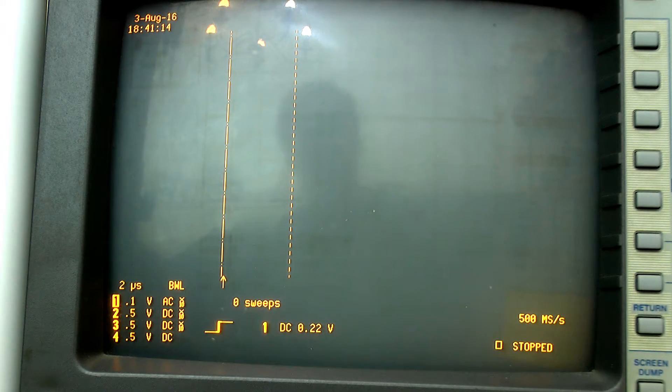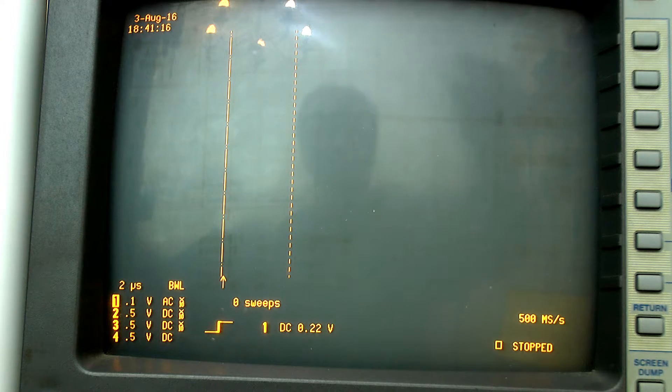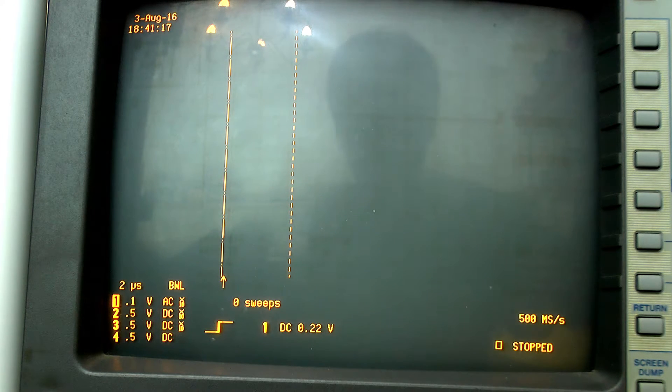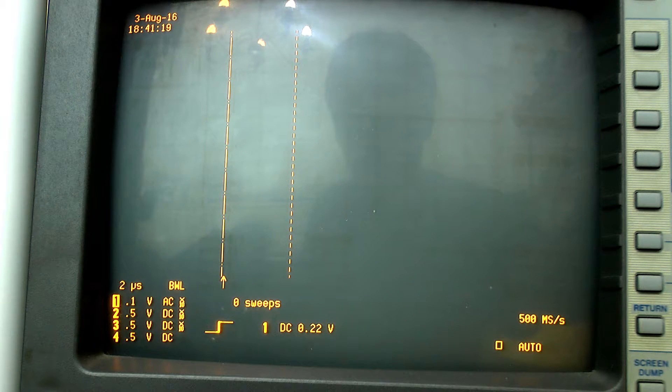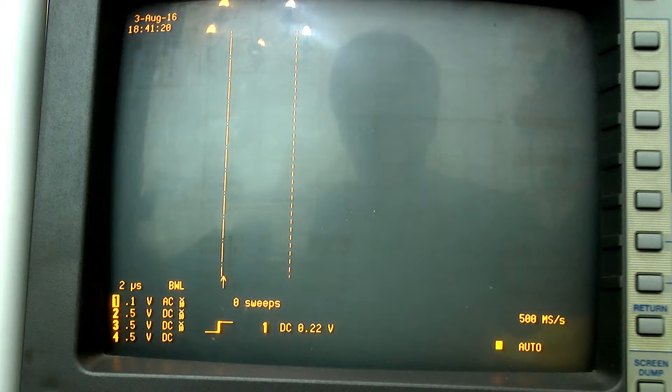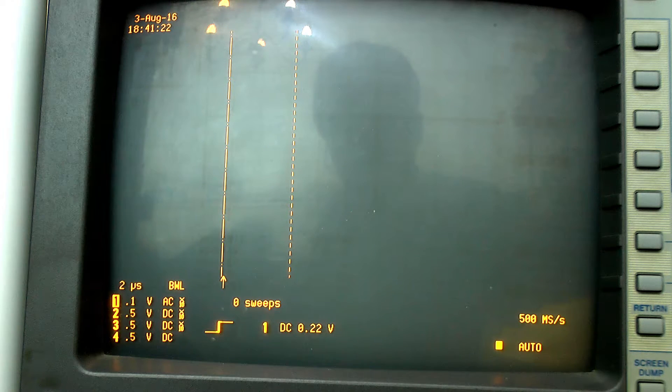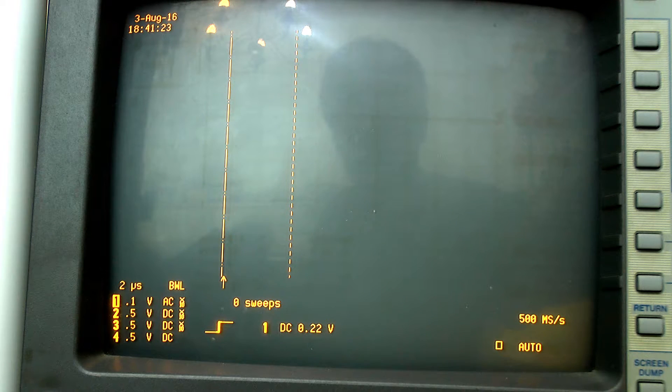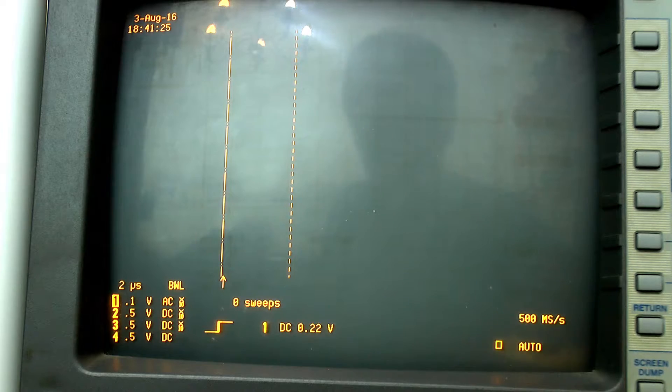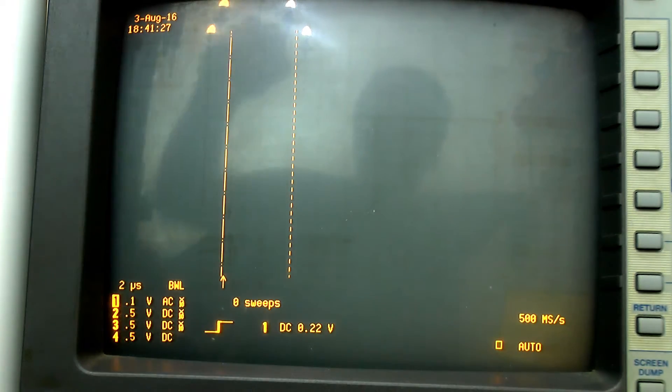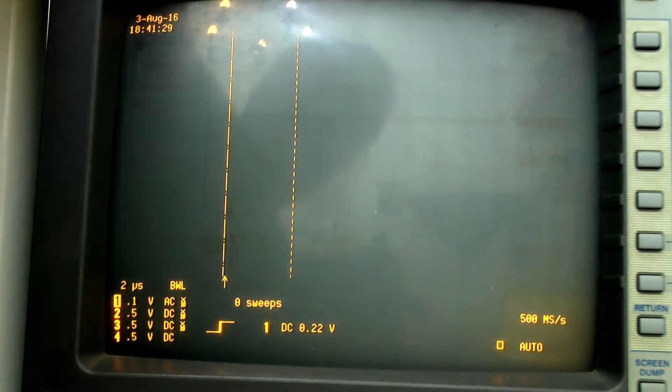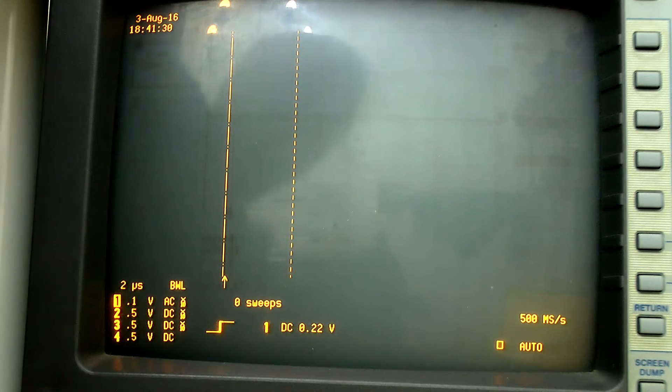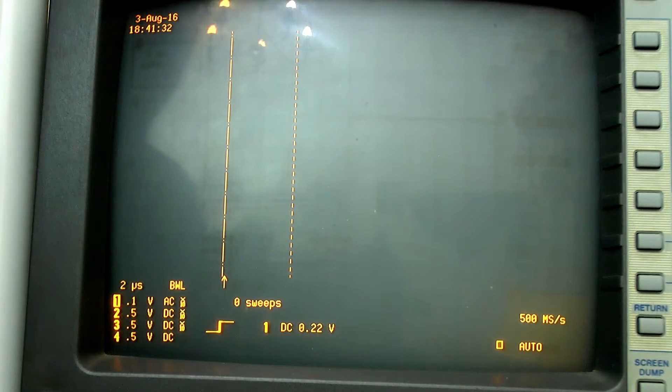And if you want to get out of the service menu, you simply press return and normally the scope should be back up. If it isn't for some reason, you simply power it off and on again to celebrate your newly found service maintenance skills.